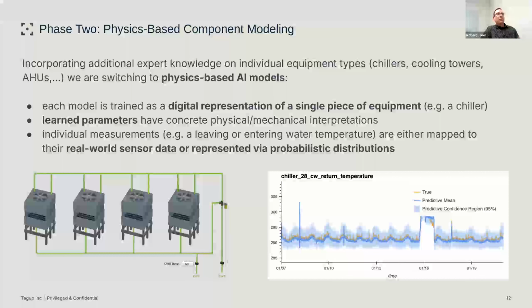Now we're switching to a truly physics-based model, where each significant piece of equipment in the system is represented by its own model. This model internally knows the basic physics of that piece of equipment - it encodes the basic rules about how a chiller transfers heat or how evaporation occurs in a cooling tower under different fan speeds.